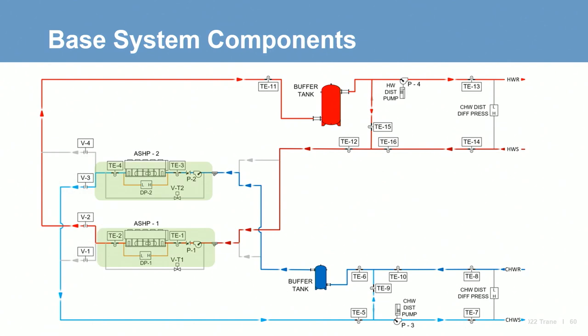In order to maintain unit stability and operate within the required compressor map, we have incorporated a heat pump bypass or tempering valve. This valve is used when the unit switches from one mode to the other and would modulate until the supply water temperature has come to within the desired range.